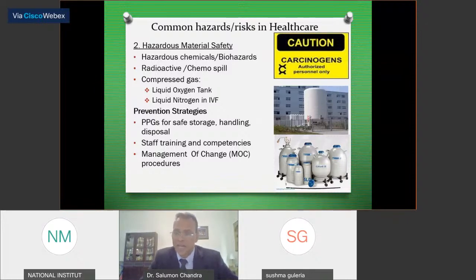You might have liquid nitrogen in the IVF center. If you have an IVF center, you might have cryopreserved embryos, and these are generally stored in a liquid nitrogen tank at a temperature of about minus 180 degrees centigrade. So you might get a cold burn if there is an exposure. The liquid nitrogen used in IVF is not a flammable gas, but it is an asphyxiant - meaning if there is a leak, the room will have less oxygen. So you may have to have an alarm system to warn you when the oxygen saturation in the room goes below 19%.